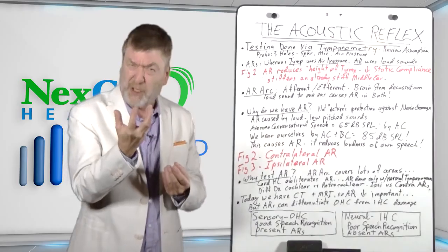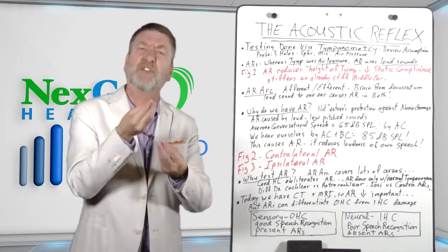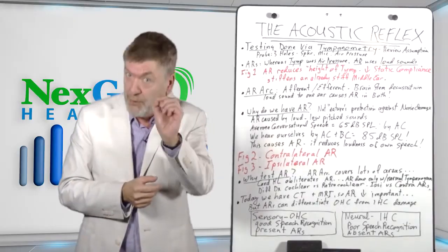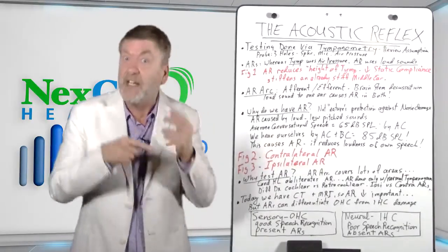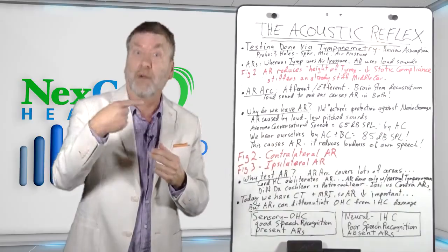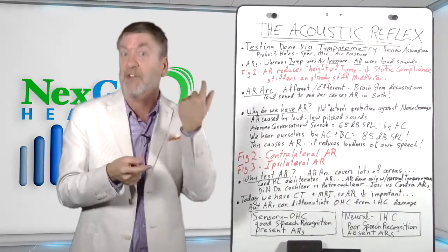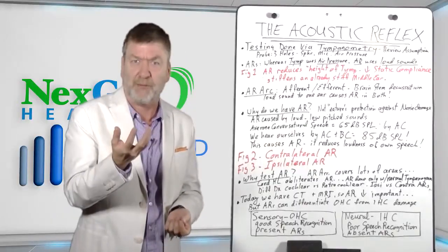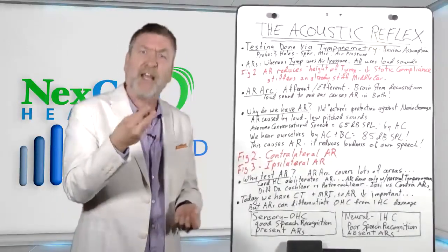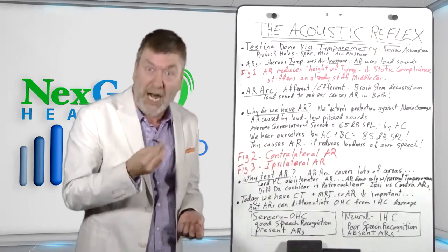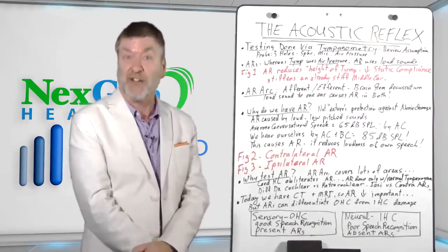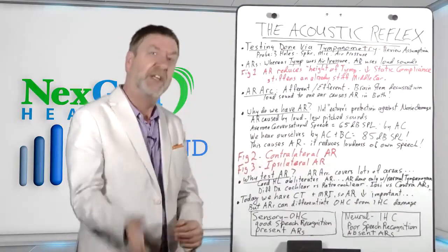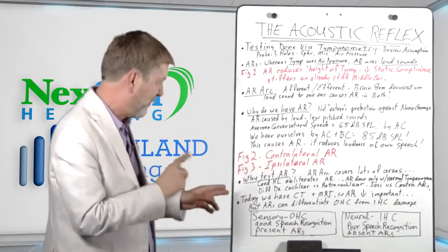So you can think of the complexity, the potential interactions between that loud stimulus used to elicit the acoustic reflex and the ongoing low-frequency tone that's constantly emitted and bouncing off the drum. There's high potential of interaction between those two tones, and that goes a long way to explaining why ipsilateral acoustic reflex measurements came later than contralateral acoustic reflex measurements. At any rate, we'll return to that in just a bit.